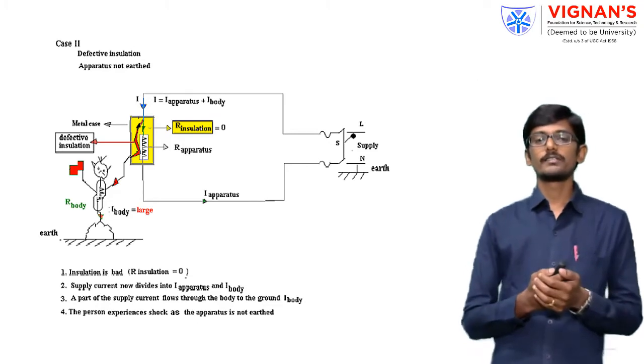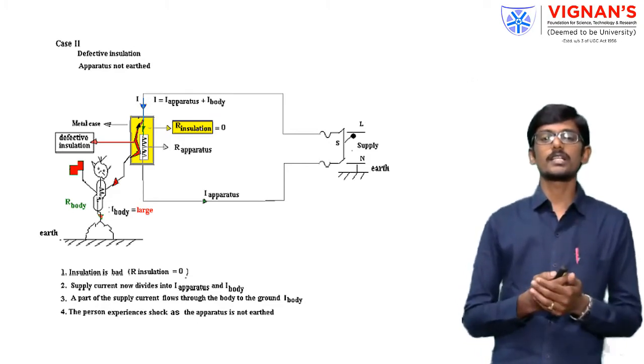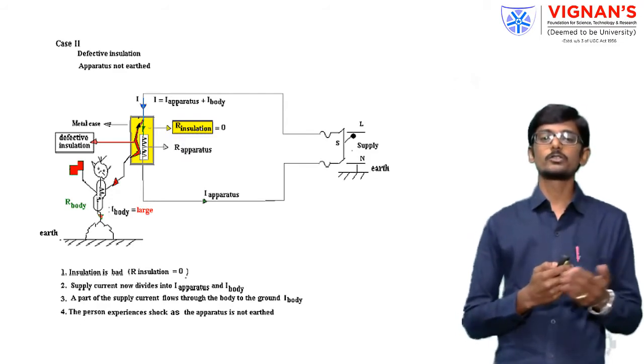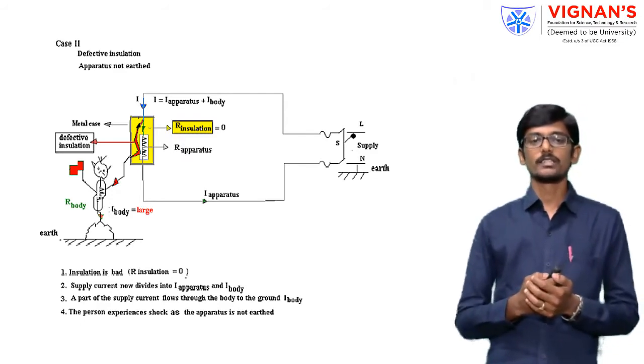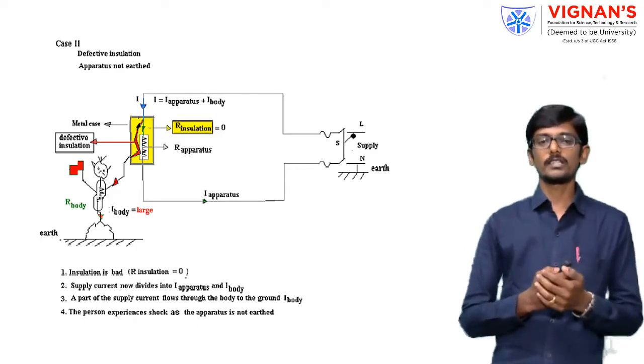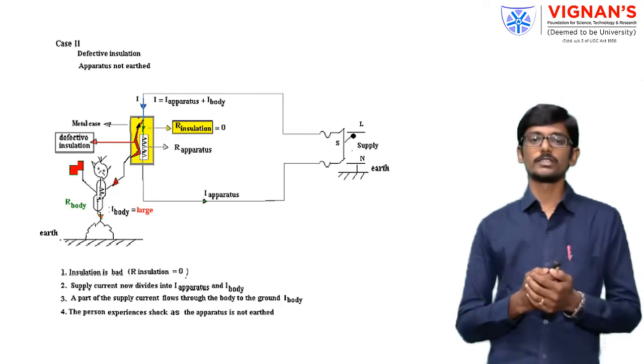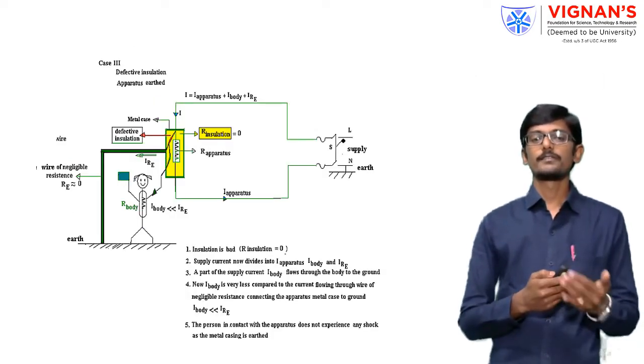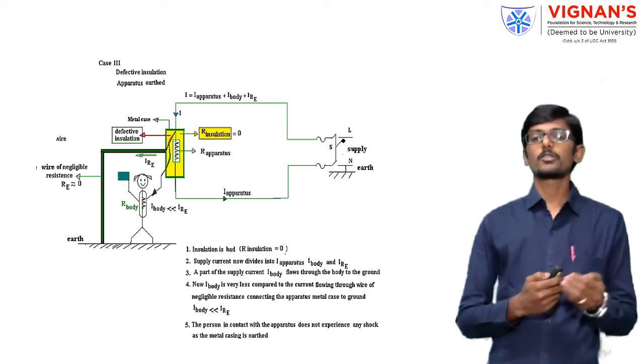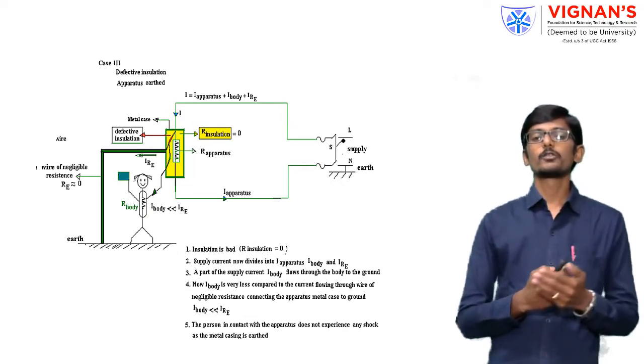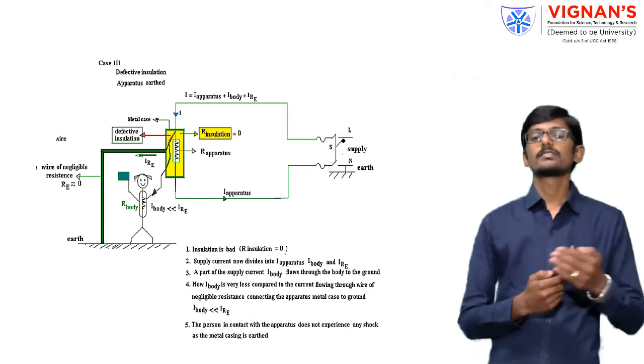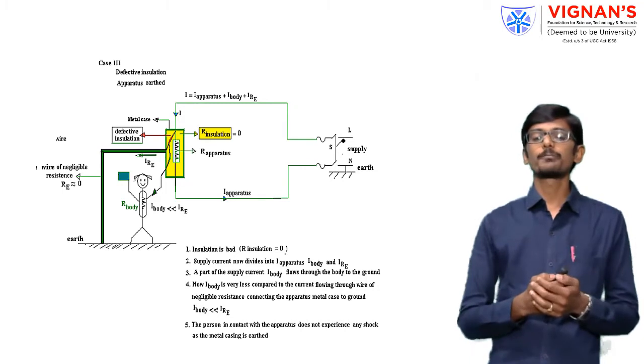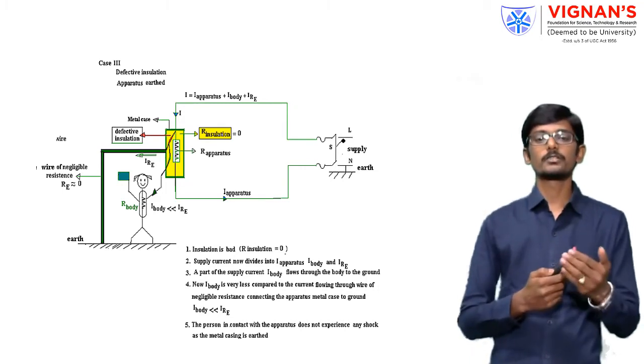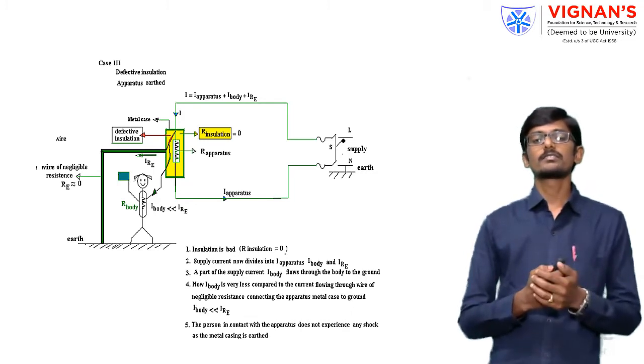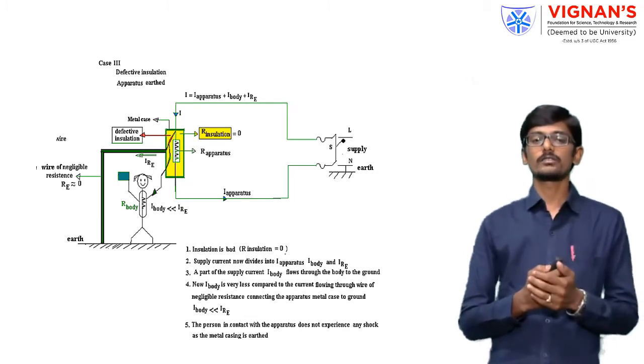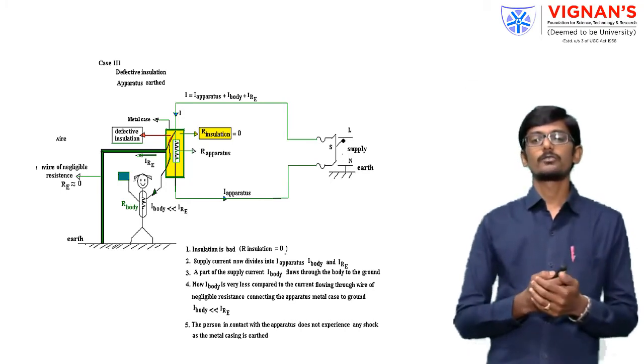So the current will be divided into 2 parts. The first one is I apparatus, and I body is the current flowing through the human who is operating that equipment. So in this case, the person may get an electrical shock due to the failure of insulation. In the third case, the insulation is defective and the equipment is protected with earthing, where the current flows through the equipment as well as the earthing system, not through the human body, because the earthing resistance is very low compared to the human body. So in this case, the human will be protected even though the device insulation becomes faulty.